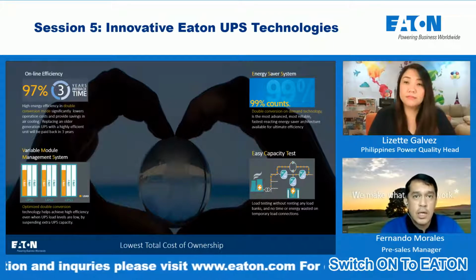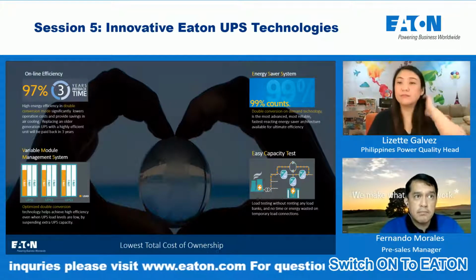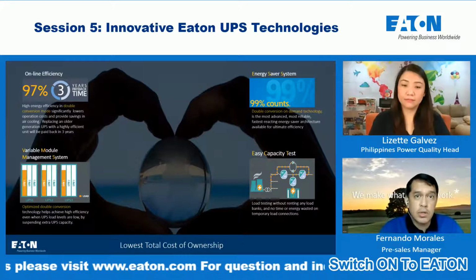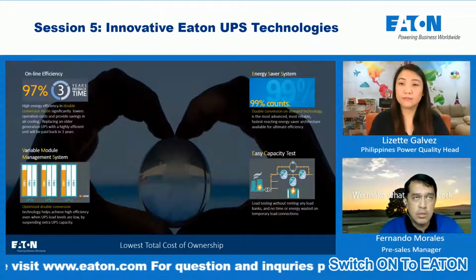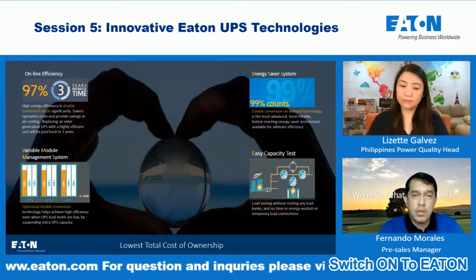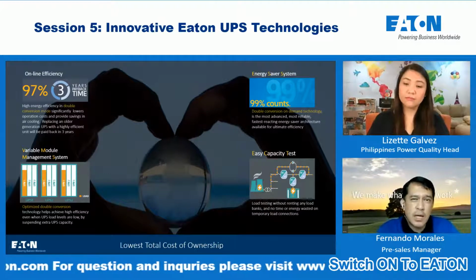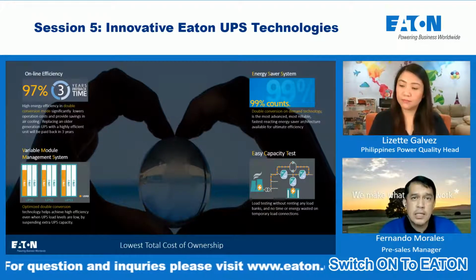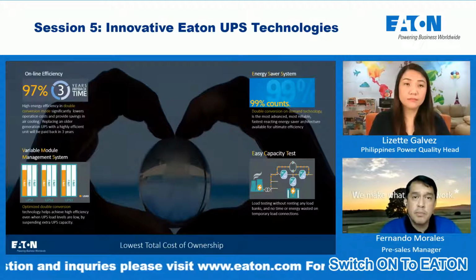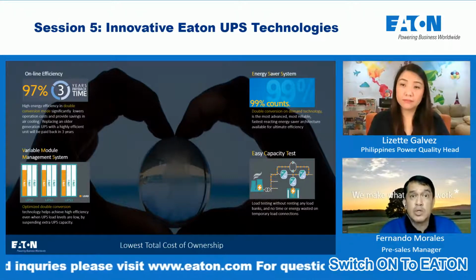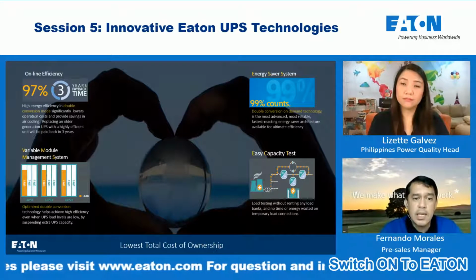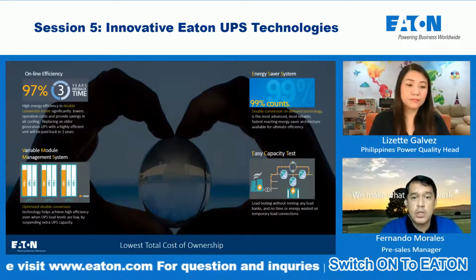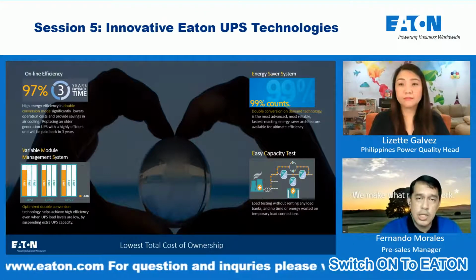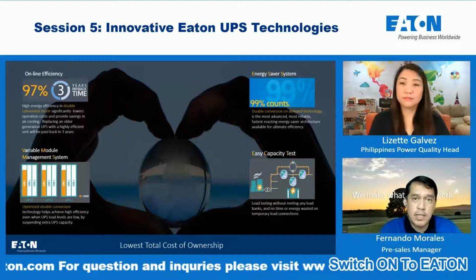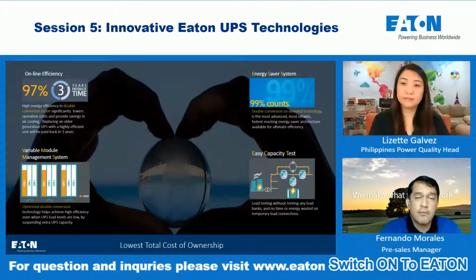So they will have savings when it comes to rental of a load bank. During the installation or commissioning of the UPS, load bank rental is one of the major contributing factors to cost. With ECT, we can help our customers save during initial startup and during annual preventive maintenance if they want to test the full capacity of their system.